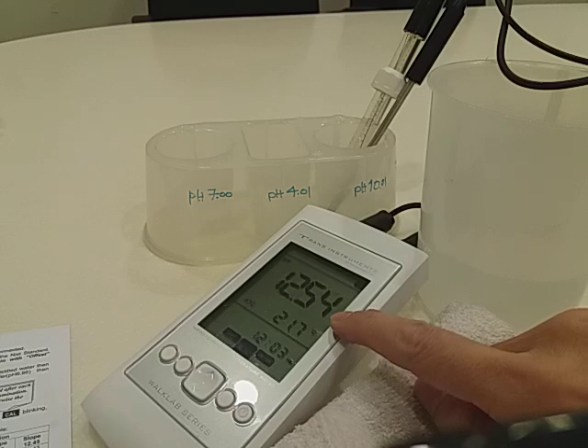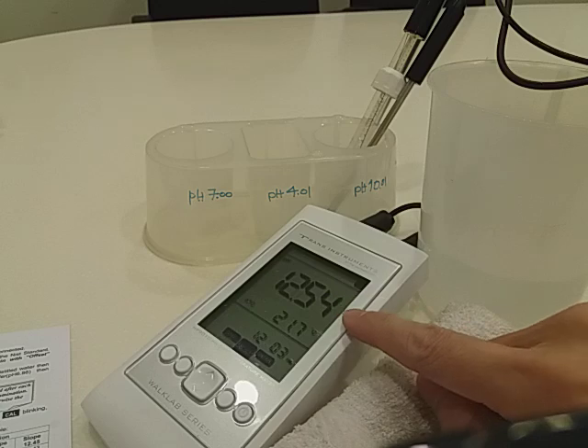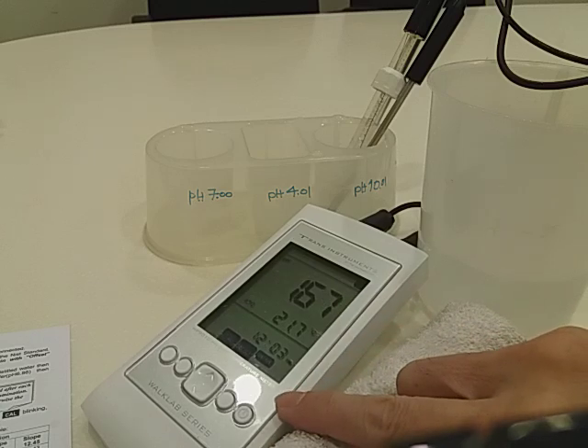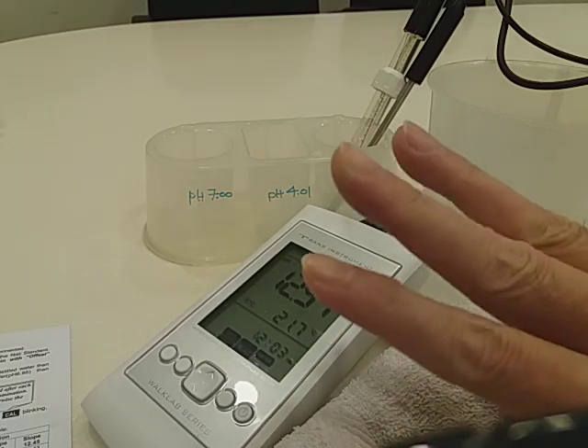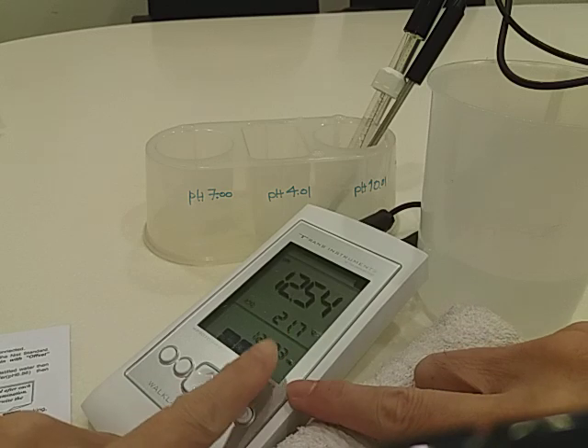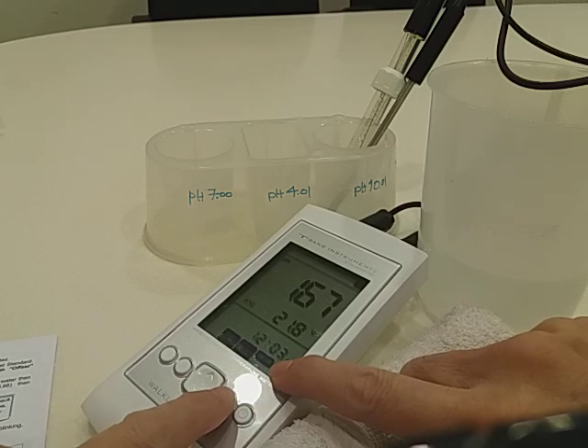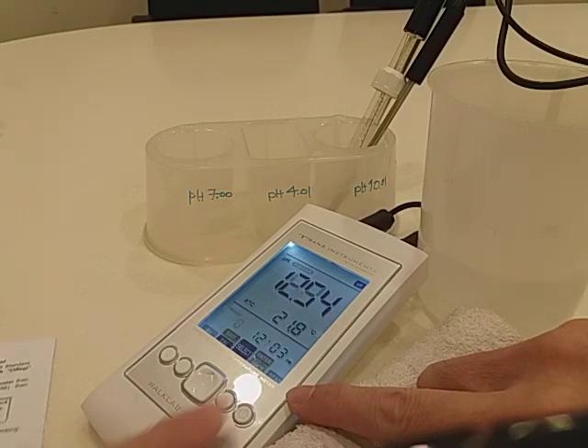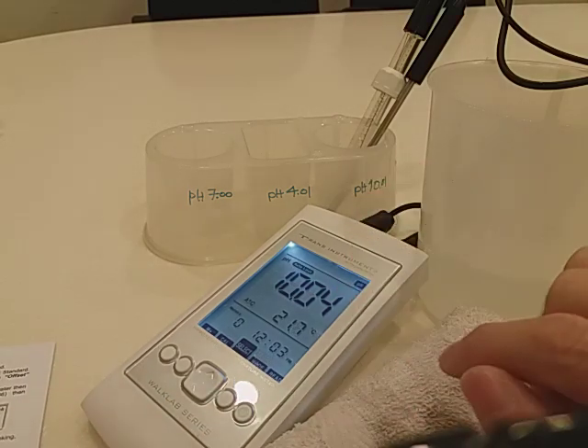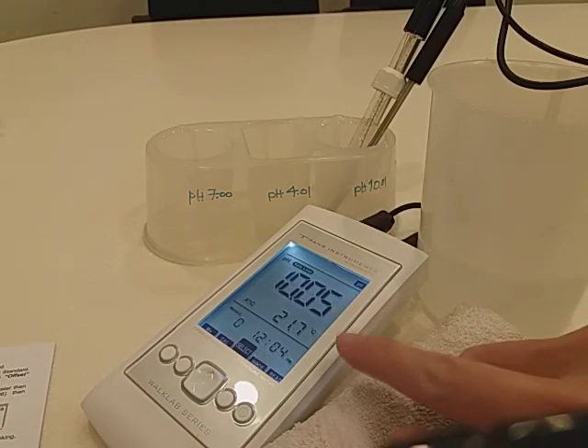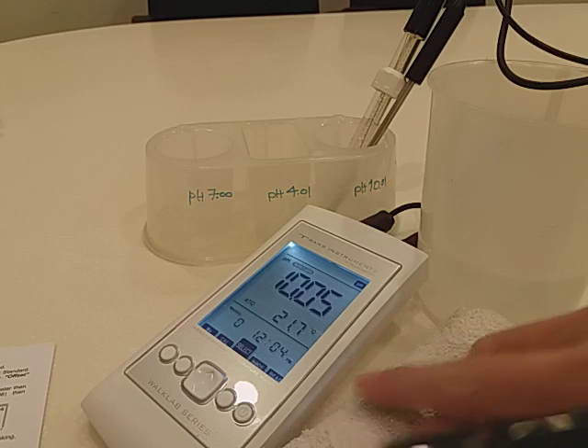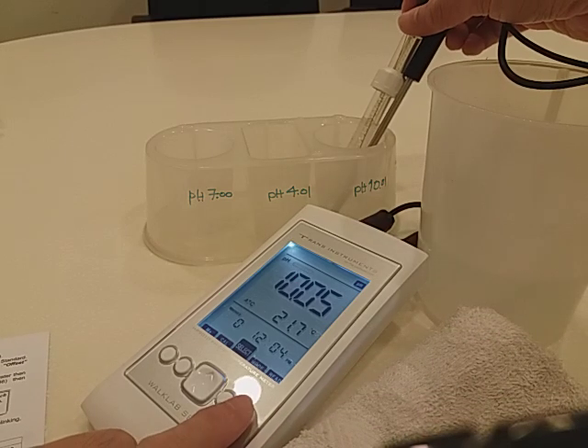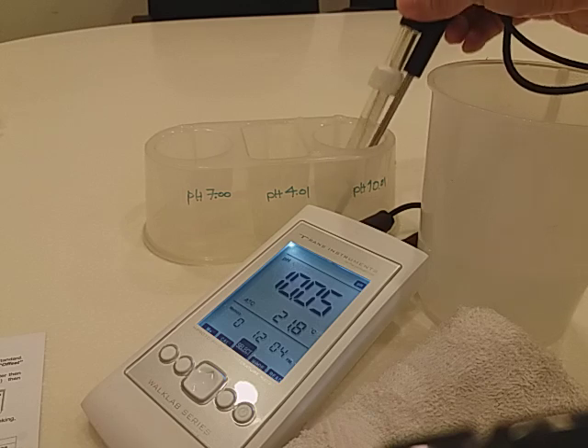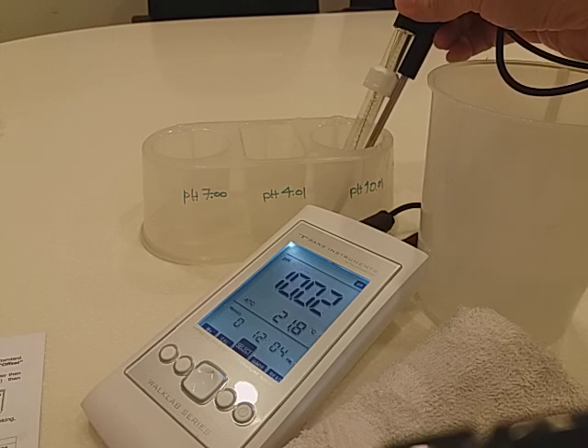Now only two other buffer solutions are left. So with that, we complete our calibration with 3 points. Very important, press the enter button and all the 3 buffers calibration points will be stored into the meter. We can press the read button one more time to check the reading once again.